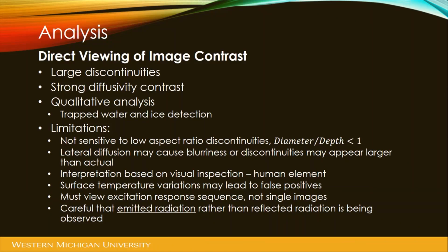So you want to take several images over time. Heat your part up, take images as it cools back down. Cool your part, take images as it warms back up. You may have to look at it at different points in time in order to see that moving through and make a determination of what's going on. And then be careful that emitted radiation is what you're looking at rather than reflected radiation.